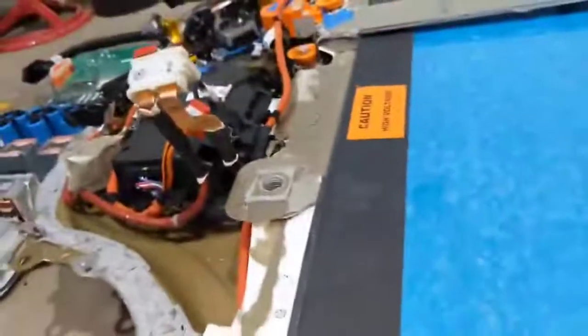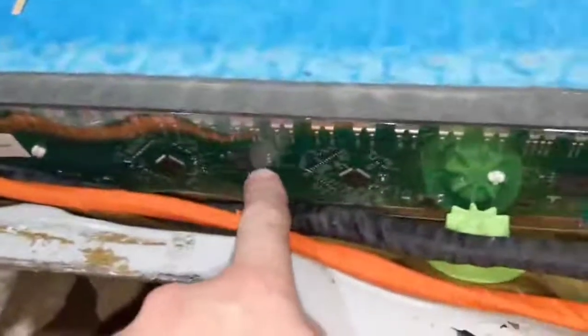There's an isolated bus here, a single twisted pair, that comes out of the BMS computer, goes through chip 1, through a galvanic isolation transformer, chip 2, transformer, and so on, all the way down in a daisy chain. If the chain is broken anywhere, the BMS can read the state from the other end, so it has some redundancy. Again, this is the same architecture, just repackaged a bit from the Model 3 and Y.